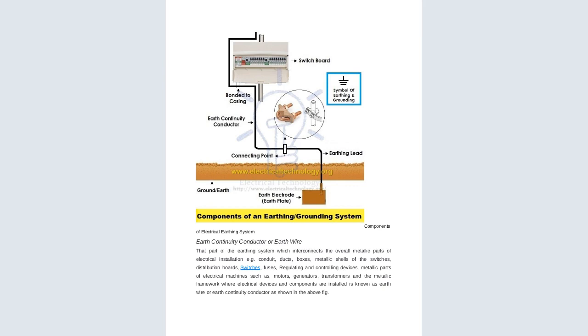The components of the earth system: now we are going to look at a drawing of how they look. Look at this drawing. This one is the switchboard, the one that is responsible for the supply of power. This is the symbol for earthing. Any time you see this diagram, you'll be seeing this symbol, and anytime you see it, it means it's an earthing symbol. And then this is the earth continuity conductor, which is normally tapped from the switchboard to the ground. This is the connecting point of the earth continuity conductor and the earth lead. This is the earthing lead, and this is the connecting point, and this is how it looks. Normally the wires meet at this point and it is tightened.